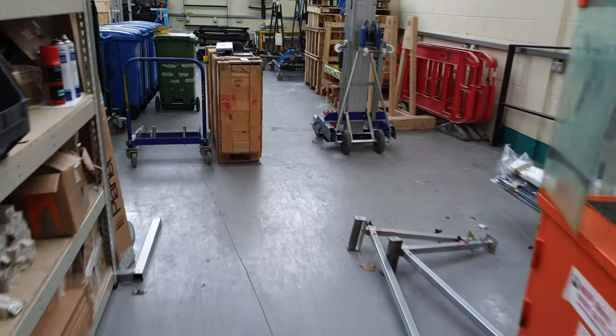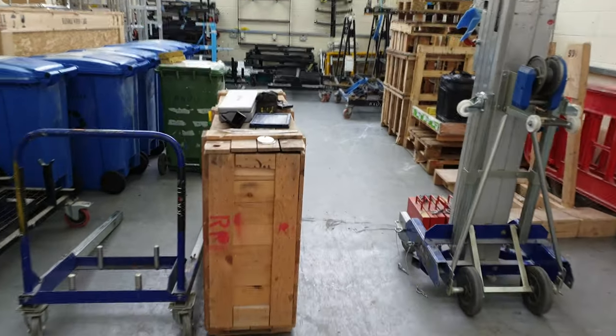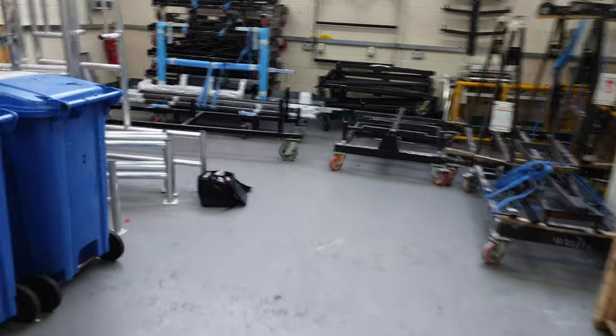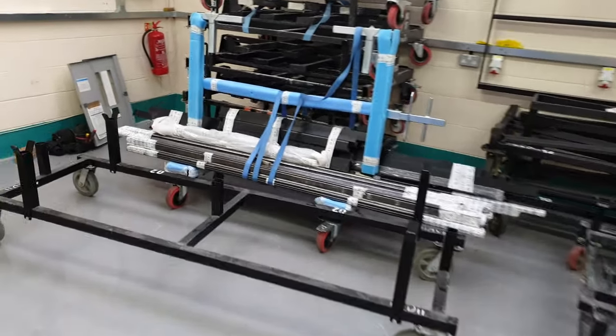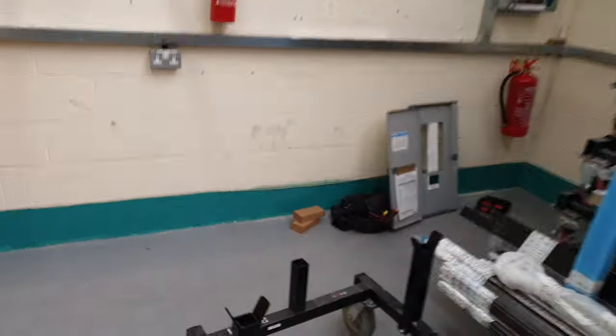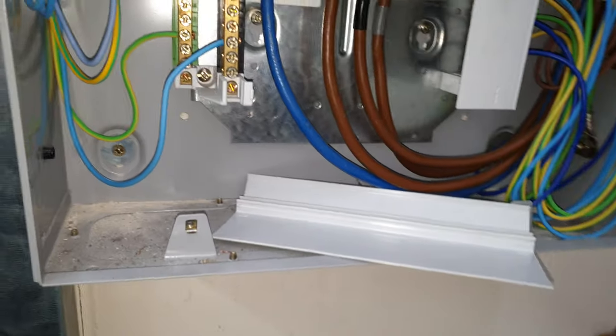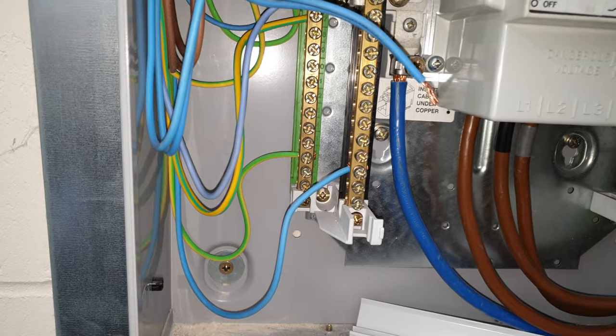A lot of the times when I go to houses and the fuse board's packed up — like the other day when I did that EICR job — the neutrals were all over the place, none of them were in order. So for the lighting, you just take out the neutral, the light goes off, and you know you've got the right neutral. That's what I've done here. Right, let's get testing.